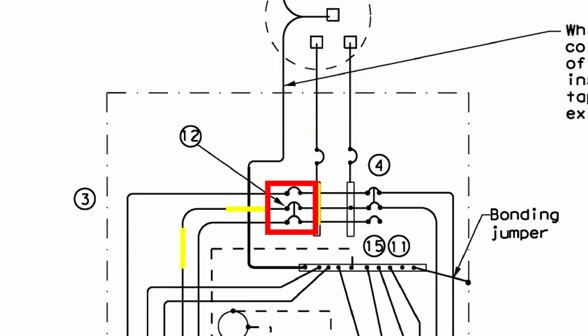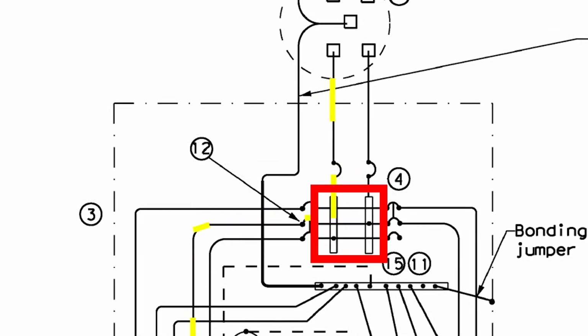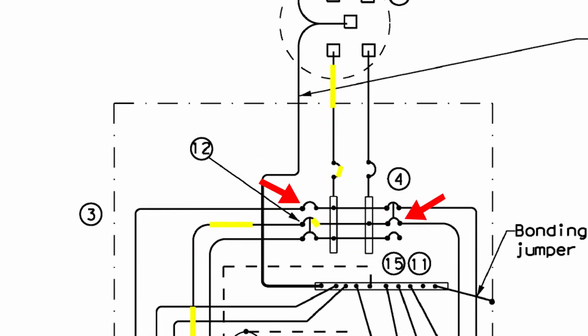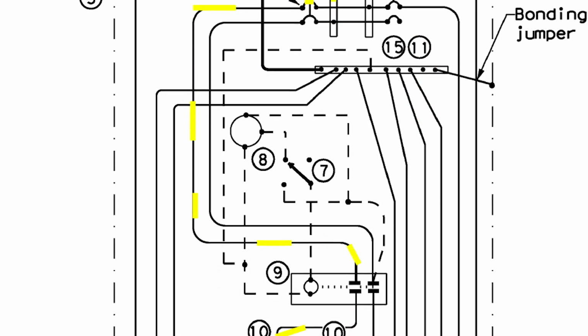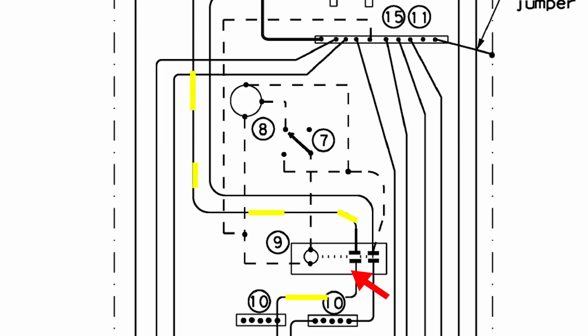They are also used as hand-operated on-off switches. The main circuit breaker protects the illumination system's components from an electrical overload. The main circuit breaker is connected to the load center's bus bars. Electrical power from this breaker is then distributed to the bus bars. 1- and 2-pole circuit breakers are attached to the bus bars and distribute electrical energy to the electrical equipment in the field. 3 components control the lighting system: the lighting contactor, a photocell, and a 3-position selector switch called the hand-off-auto, or HOA switch.